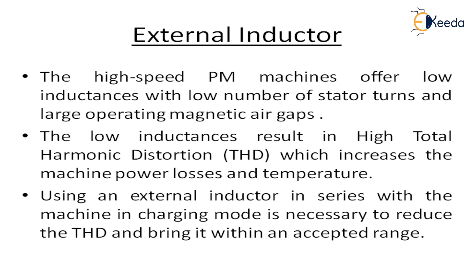within an accepted range. Whenever the high speed permanent magnet machine offers low inductance, what happens? Low inductance means a low number of stator turns, so there will be a large operating gap. So the THD is very high, and there will be a loss in the machine. So we connect one external inductor to compensate the THD. Usually for voltage THD we want plus or minus 5 percent; above this we can't accept it.